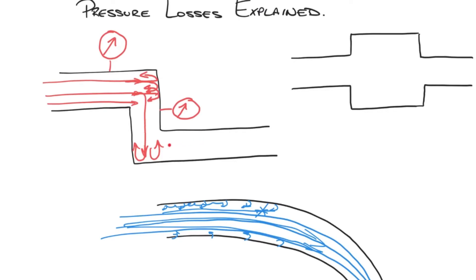We see another pressure drop on each corner until the oil flow finally gets through. Each of these pressure drops across the 90-degree fittings adds up. Back at the pump, the pressure protection valve may open, and the load downstream gets less pressure because pressure is being dropped across all those 90s along the way. Even with high pressure at the pump outlet, by the time it reaches the motor or cylinder, each 90-degree fitting has taken some of that pressure away from the effective downstream load.